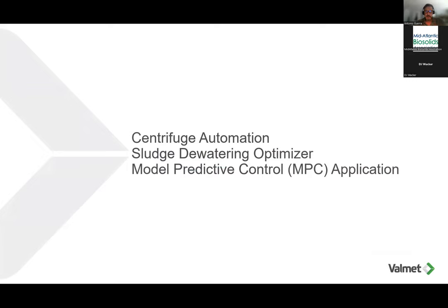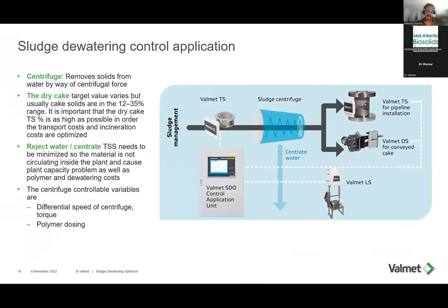So focusing on the centrifuge and dewatering process, there is definitely some optimization upside to enabling measurements and control algorithms when trying to minimize your costs in this area. If you look at a typical dewatering sludge centrifuge, basically the whole purpose of the centrifuge is to remove solids from water by way of centrifugal force. There are various streams coming in and out of that centrifuge. From the left side, you have the feed stream, which I mentioned is a good place for a density or solids analyzer. Together in series with an existing flow meter, you start to enable mass calculations. So you know the mass of solids as opposed to the volume of the stream coming into the system.